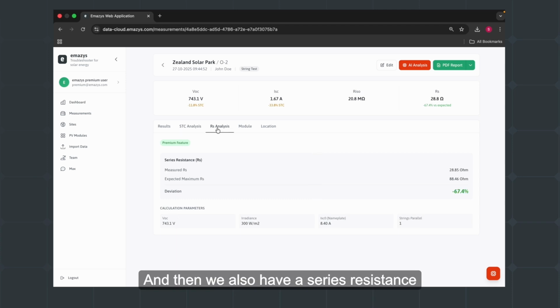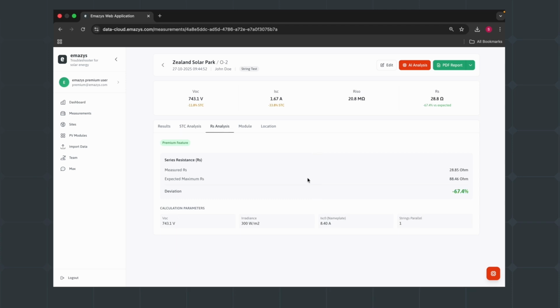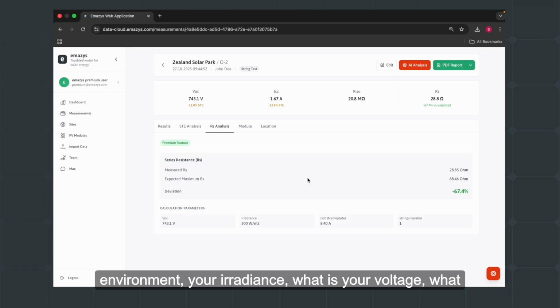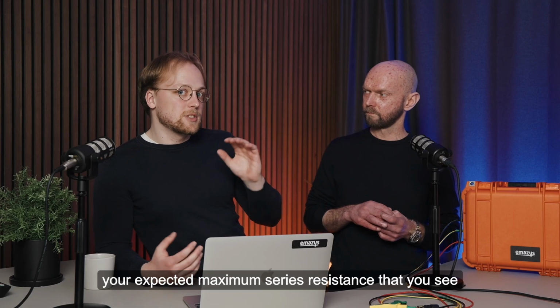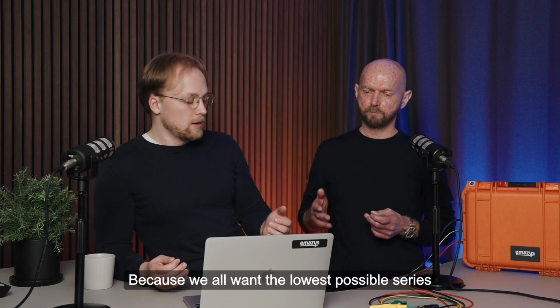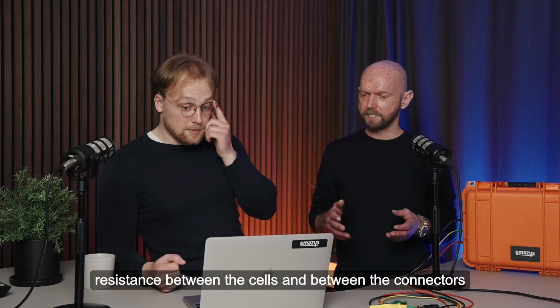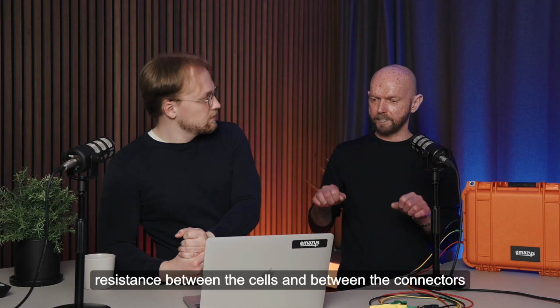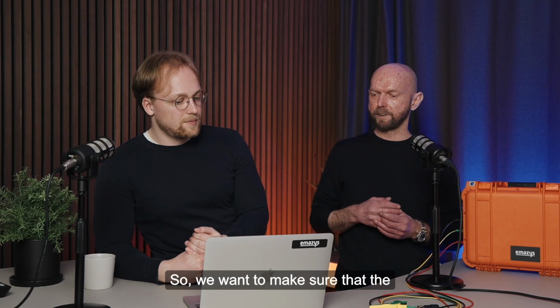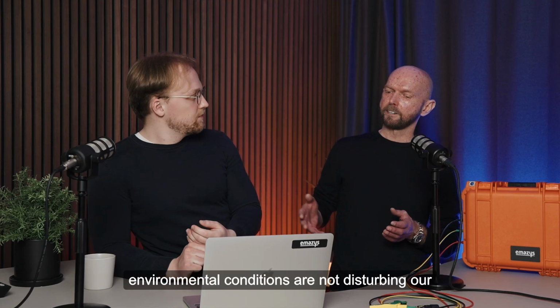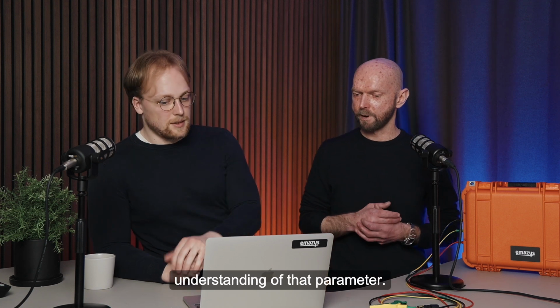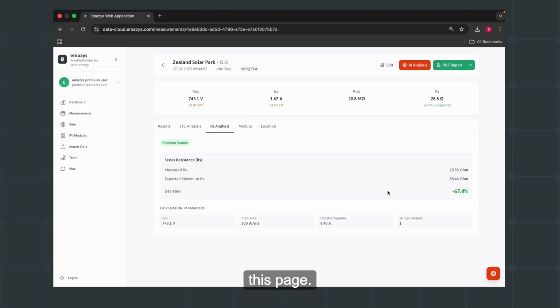Yes, exactly. And then we also have a series resistance analysis. This is where we look at your environment, your irradiance, your voltage, and your module, and then we can calculate based on those conditions what your expected maximum series resistance should be in your system. Okay, because we all want the lowest possible series resistance between the cells and between the connectors and so on. So we want to make sure that the environmental conditions are not disturbing our understanding of that parameter. Exactly. So lower is always better. Yeah. So this is what we can see on this page.